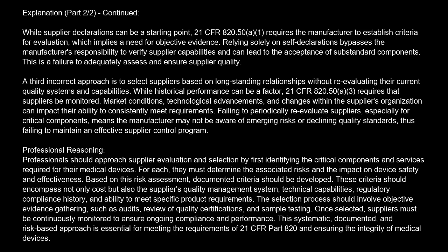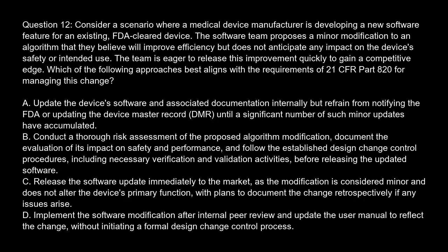The selection process should involve objective evidence gathering, such as audits, review of quality certifications, and sample testing. Once selected, suppliers must be continuously monitored to ensure ongoing compliance and performance. This systematic, documented, and risk-based approach is essential for meeting the requirements of 21 CFR Part 820 and ensuring the integrity of medical devices. Question 12.